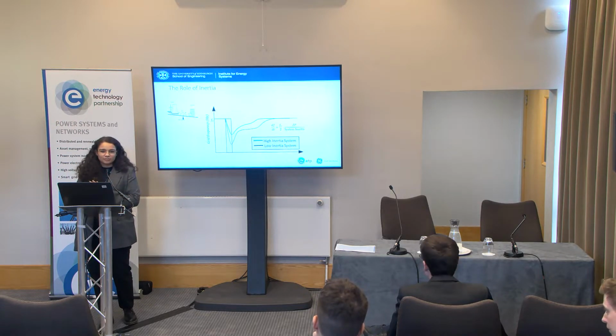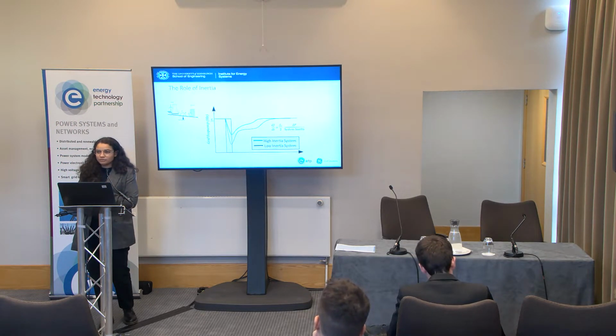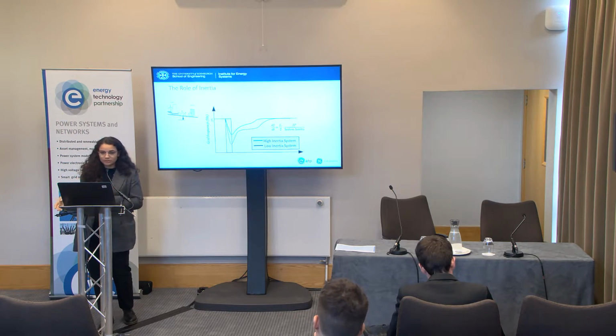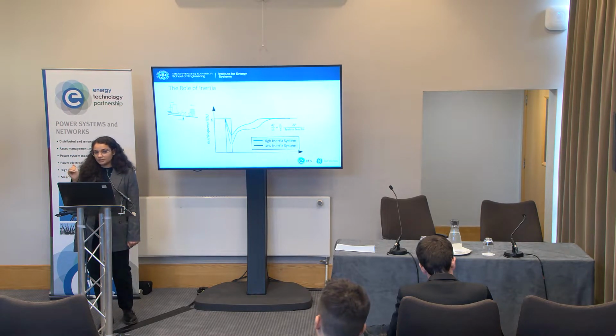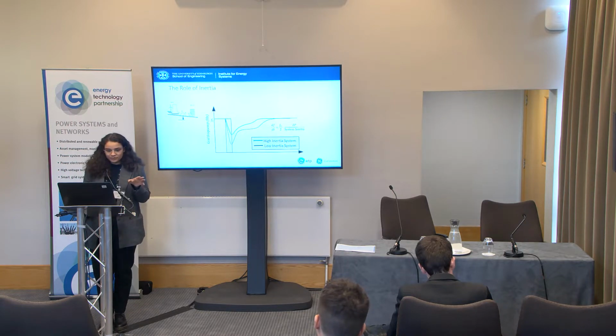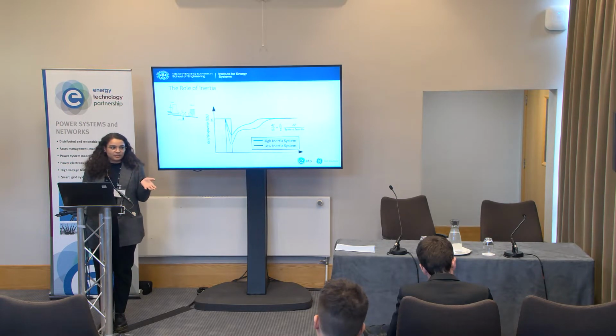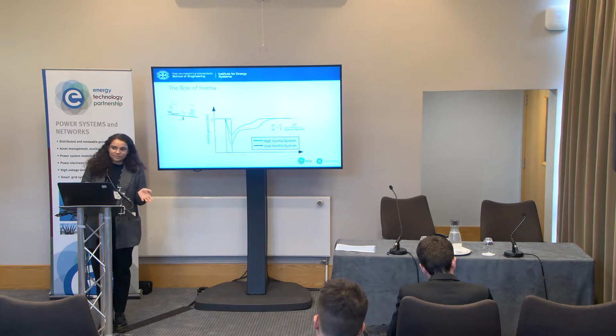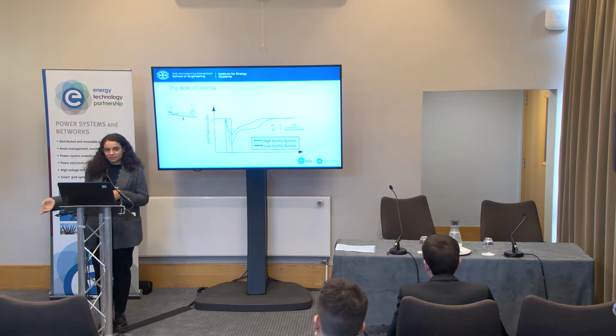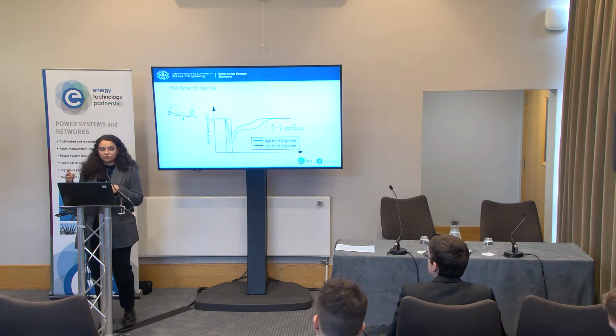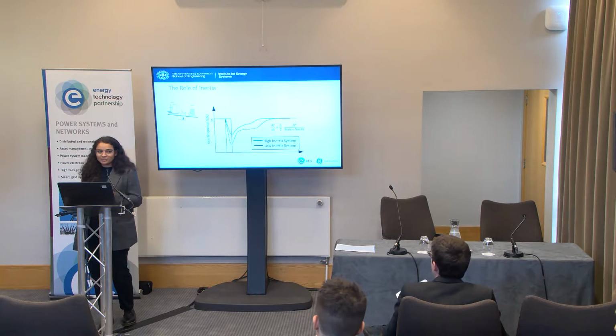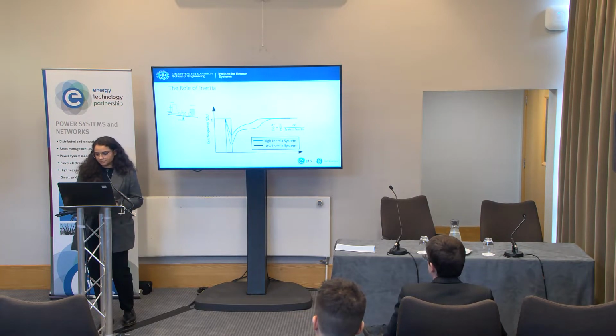I don't know if anybody remembers, there was a really big power cut in August 2019, I think. All the trains in King's Cross stopped going places. And in their report, National Grid listed low system inertia as a contributor to that. So that's why we want virtual synchronous machines. These would be converters whose control mimics the behavior of a synchronous machine, so that we can reduce the problems of low inertia without actually having hydrocarbons connected.